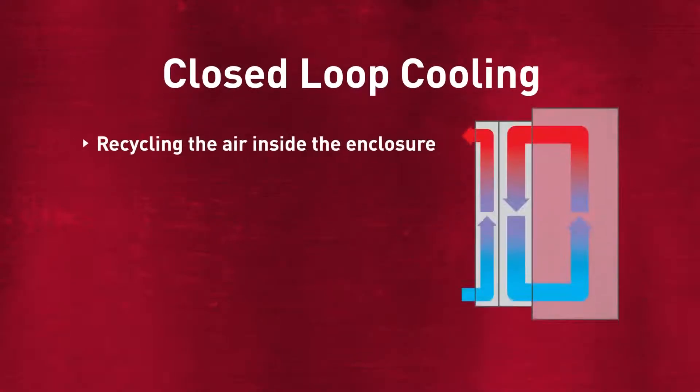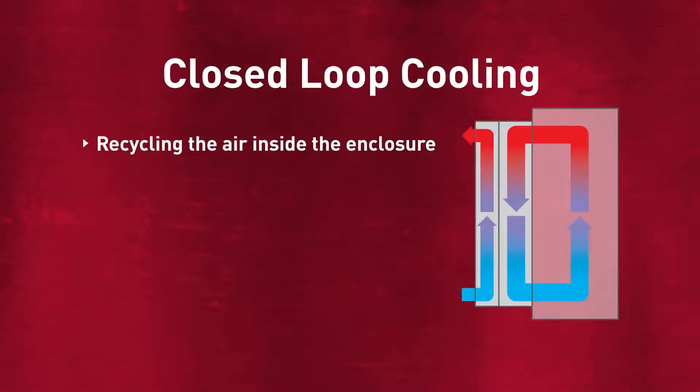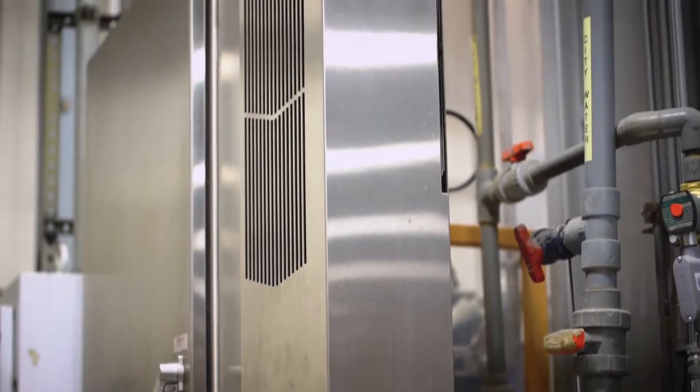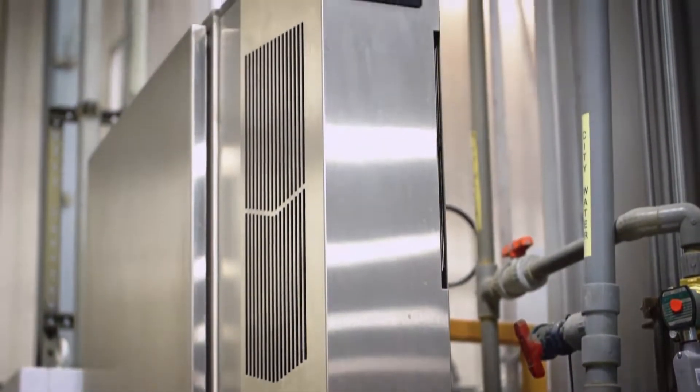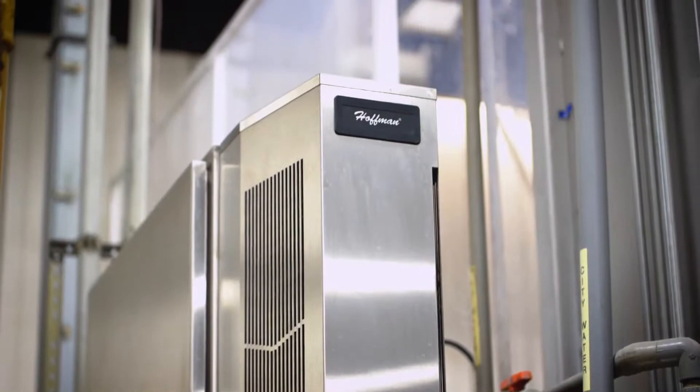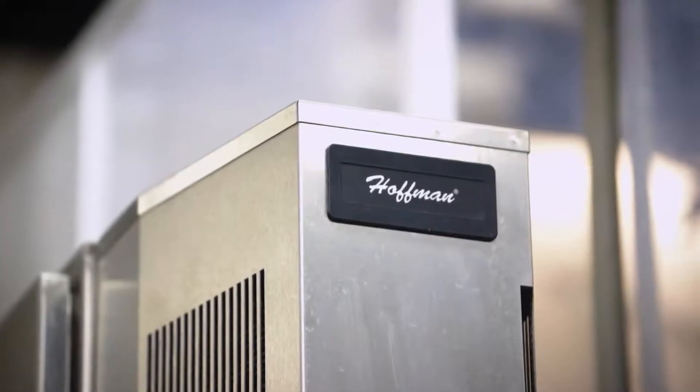In a closed-loop situation, what you are doing is recycling the air inside the enclosure. By recycling the air inside the enclosure, you're not introducing moist outside air, protecting your equipment from dangerous contaminants and dust. Closed-loop cooling doesn't have to be an air conditioner — it can be a heat exchanger as well. The big thing about closed-loop cooling is maintaining the integrity of the air inside the enclosure.